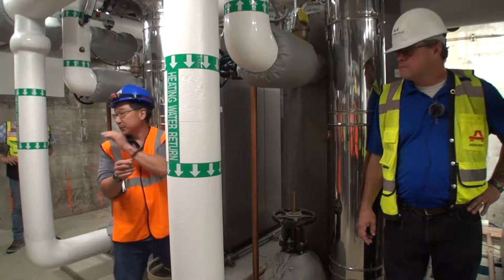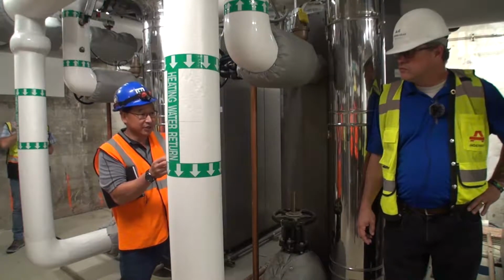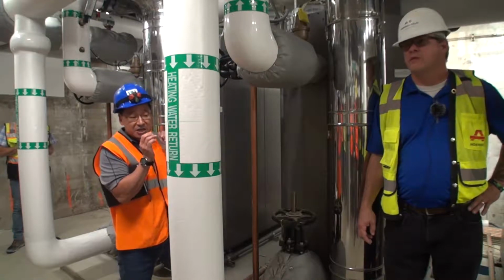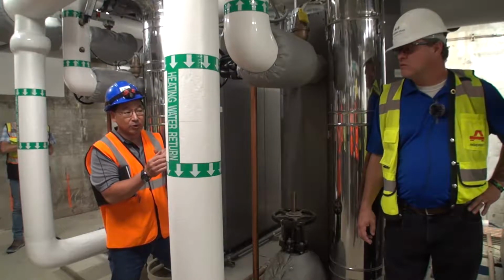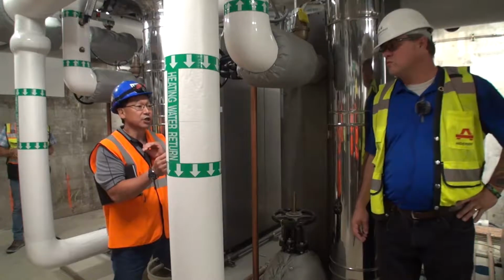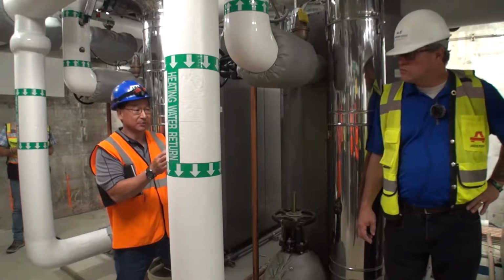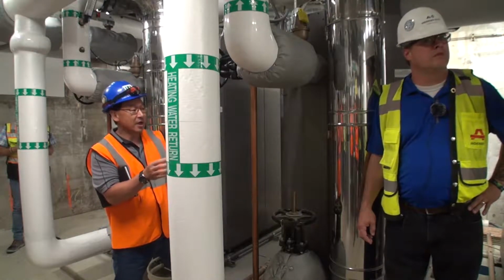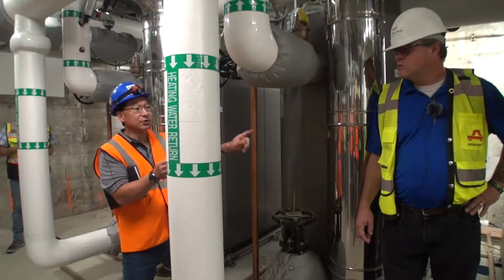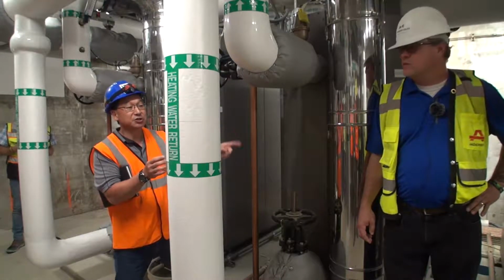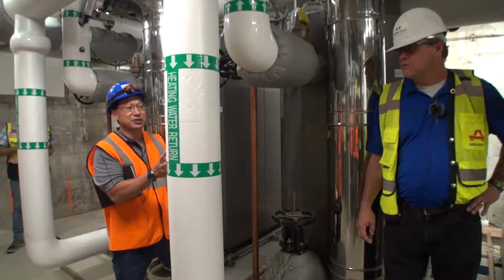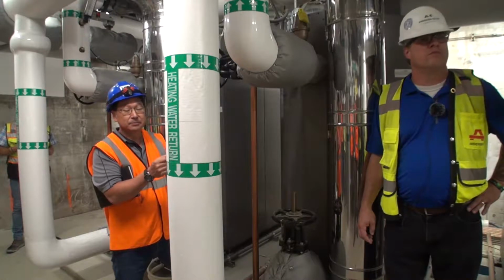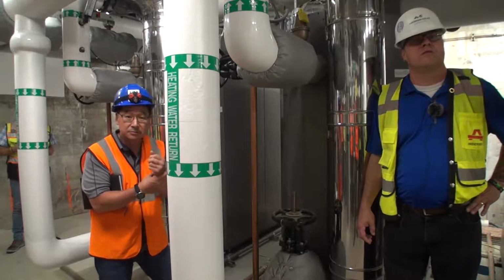If there is a problem, and we went over that previously at the school, if you have an issue with a boiler and it's in fault, leave it in fault, don't kill the power, leave them on. That way, these boilers are all communicating with each other. It knows it's in fault. If you turn it off, it doesn't know. What if you have a problem that needs to be locked out?